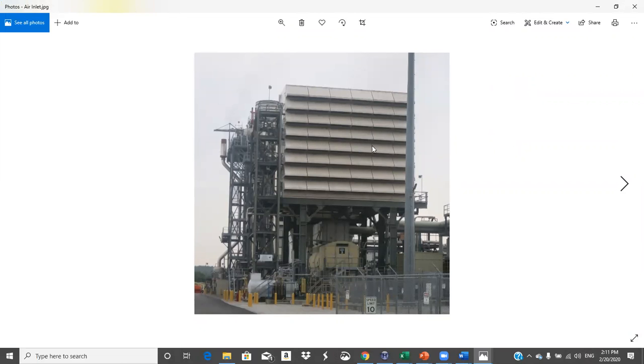Okay. So this is where the air enters that is going to go into the gas turbine. And inside this thing, there are filters and evaporative cooling media. The air gets filtered and goes through that media, and there are pumps over here, not very big, like 20 horsepower pumps or something, that pump water up, like distilled water, because you want to keep all this stuff as clean as possible. It wets this media, and when the air flows through that, it evaporates. It's an evaporative cooler. So in the summertime you can cool down that air. If you cool down that air, it's denser, and you put more molecules into your gas turbine cycle, and you get more power out.